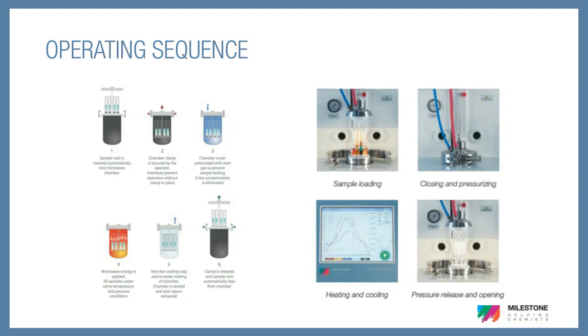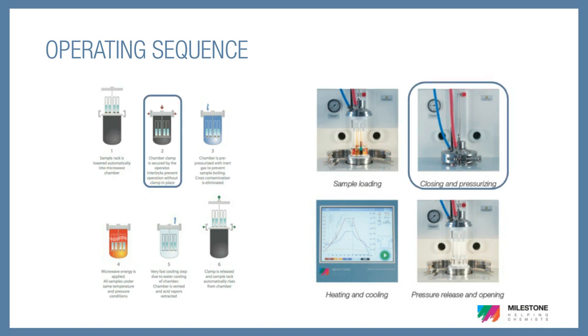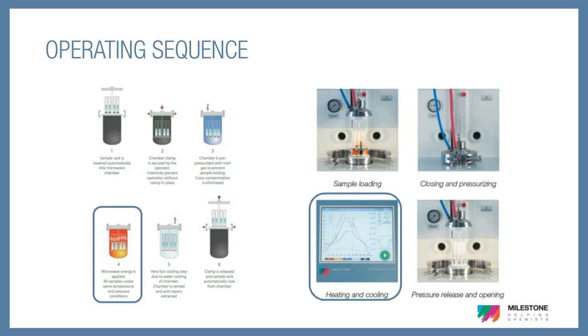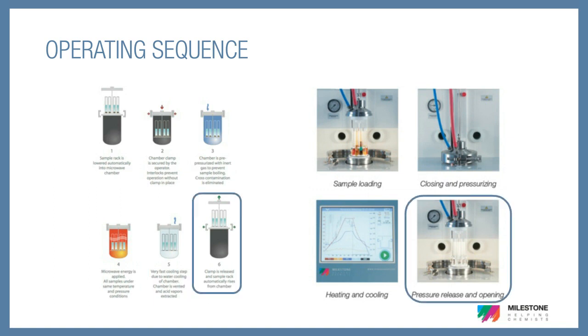Now let's take a closer look at the system's operating sequence. First, you weigh your samples into vials. This can be done directly on an analytical balance, add reagent, and place the loose-fitting cap onto the vial. Next, the rack is lowered into the reaction chamber containing the baseload. The system is clamped and pre-pressurized to 40 bar, which not only acts as a gas cap, but also prevents cross contamination between the samples. Next, the microwave program is started, and our samples are digested. Once the digestion program has completed, the Ultrawave will utilize a powerful external chiller, which accelerates the cooling process. Once the system has cooled to about 80°C, it will automatically depressurize. Once depressurized, we open the reaction chamber to remove our samples and put them onto the ICP or ICP-MS.